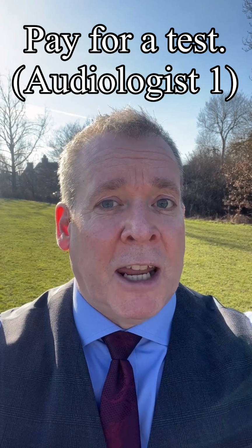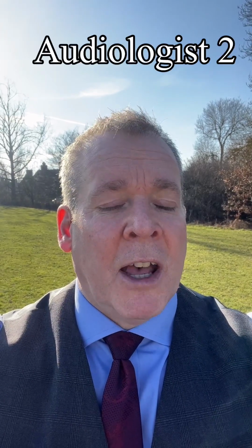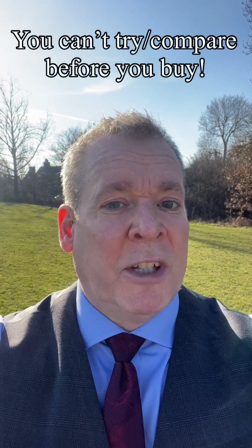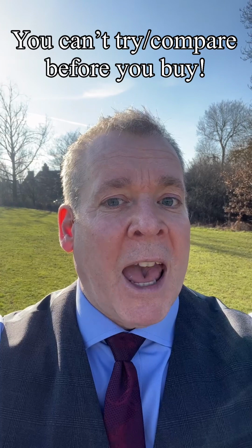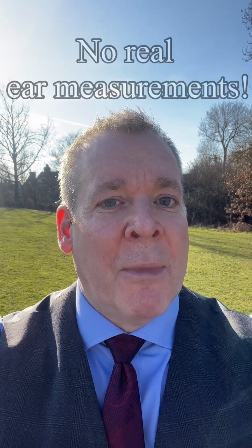So firstly, if someone is going to post you out pre-programmed hearing aids, the first thing you've got to do is go and have a hearing test with somebody. Now, if you come to someone like us, we're an independent audiology clinic, there's going to be a cost involved. Secondly, when they send the hearing aids out to you, if they're pre-programmed, they're programmed as if they've been programmed for an artificial head, so a dummy. Now, will this dummy head have the same ear anatomy as you? We don't know. The only way to know will be to do real ear measurements.